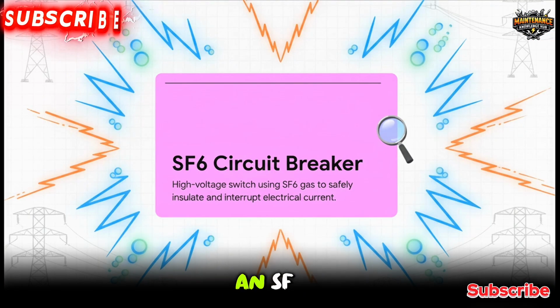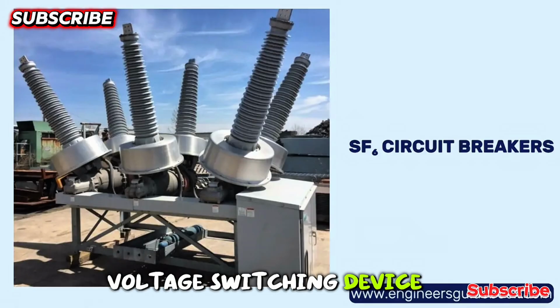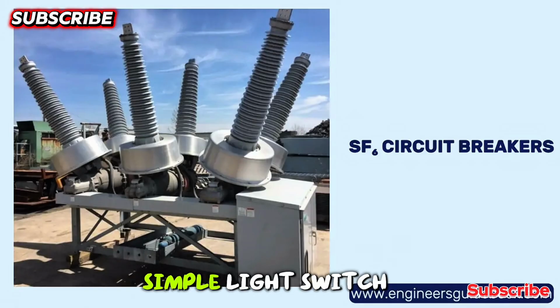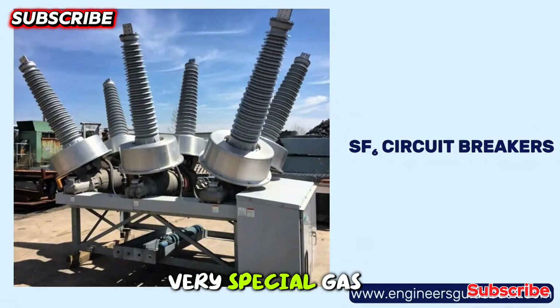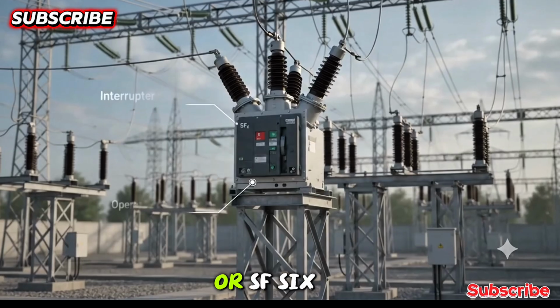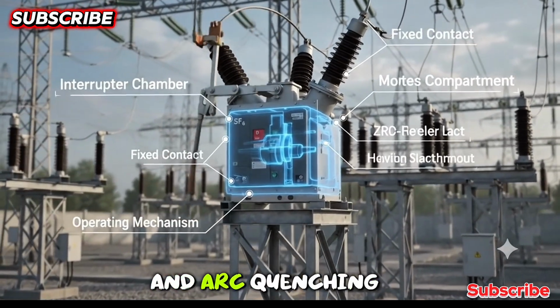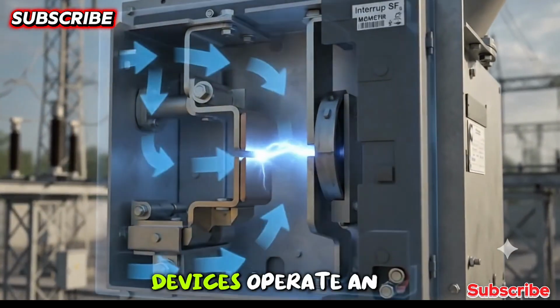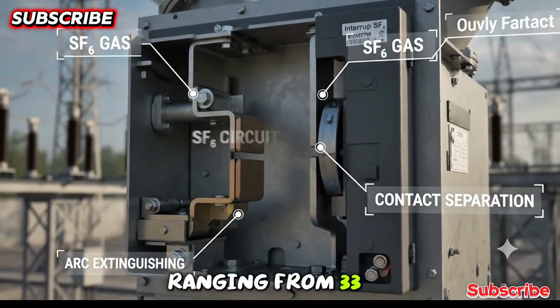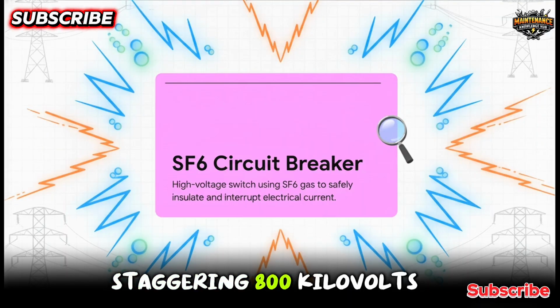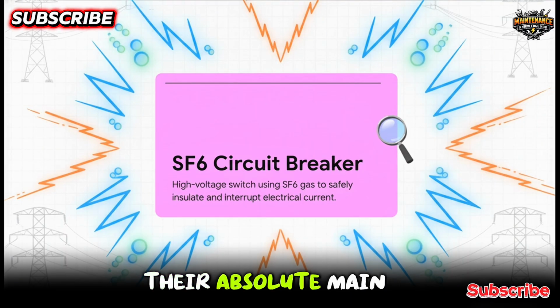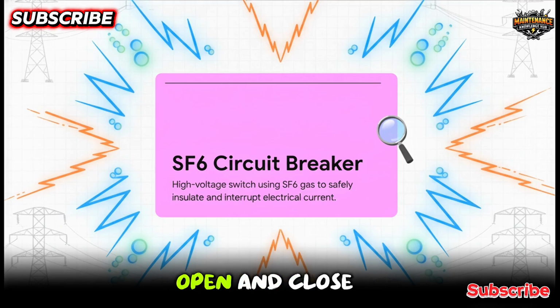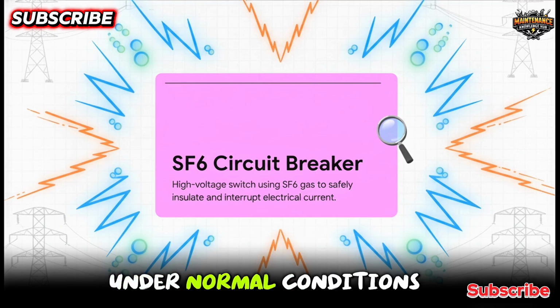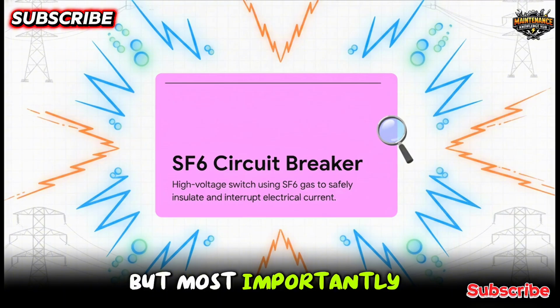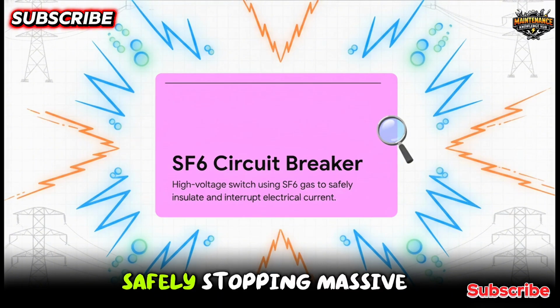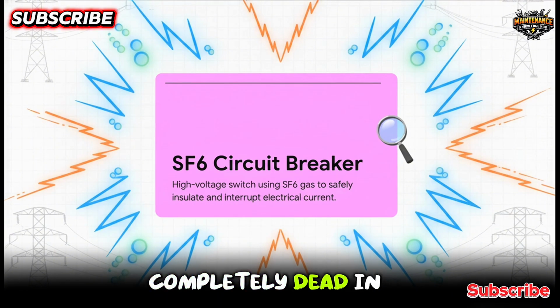So fundamentally, an SF₆ circuit breaker is a high-voltage switching device. But listen, it is definitely not like the simple light switch on your wall. It uses a very special gas called sulfur hexafluoride, or SF₆ for short, as its insulating and arc-quenching medium. Now, these heavy-duty devices operate in electrical networks ranging from 33 kilovolts all the way up to a staggering 800 kilovolts. Their one job, their absolute main purpose, is to safely open and close electrical circuits. They do this under normal conditions, sure, but most importantly, they do it during extreme fault conditions, safely stopping massive electrical currents completely dead in their tracks.